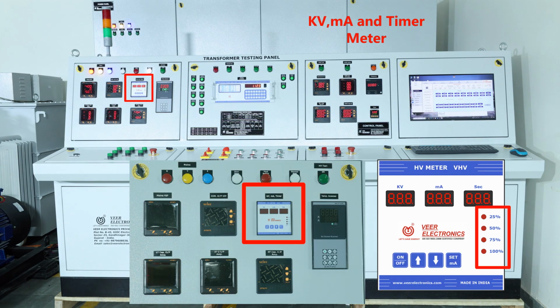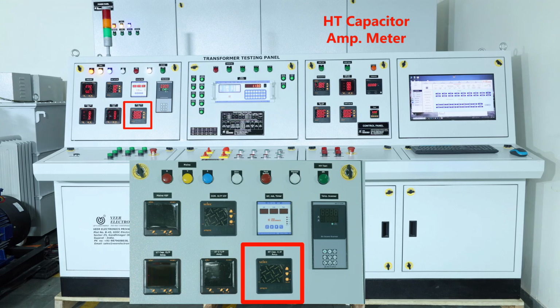We provide 4 tripping ranges in the HV meter, like 25%, 50%, 75% and 100% of total leakage current. This is the on-off push button to turn on and off the HV test. This is the up and down arrow push button. It is used to set time during the test. This is the milliampere selection push button. This is the HT capacitor bank output ampere meter, measured by capacitor CT.